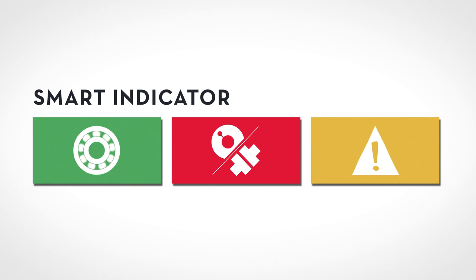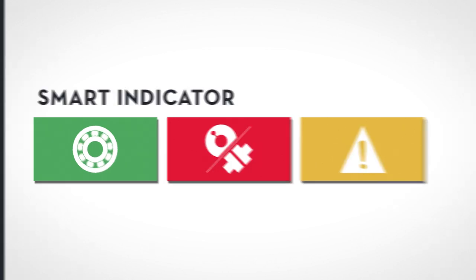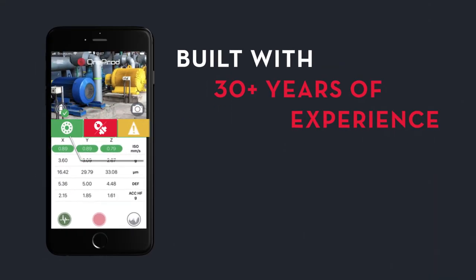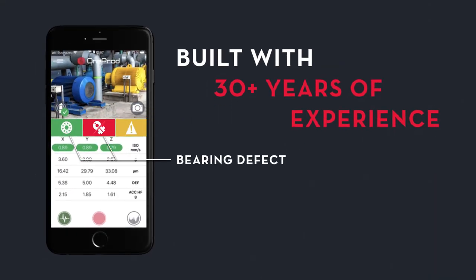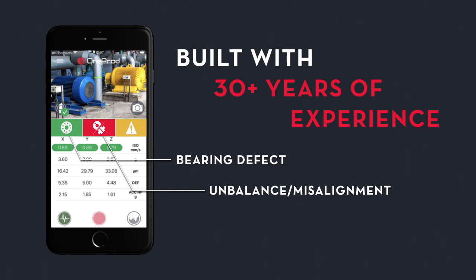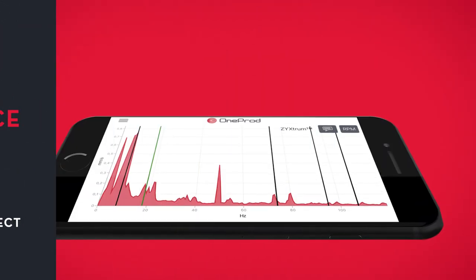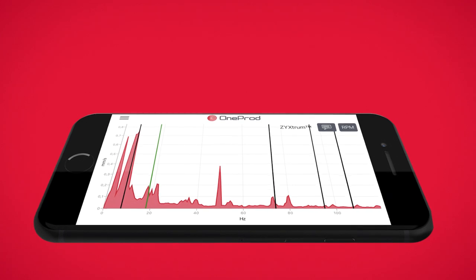In addition, results are displayed in the form of a smart indicator, which will indicate if there is no bearing defect, unbalance or misalignment, or a miscellaneous defect.